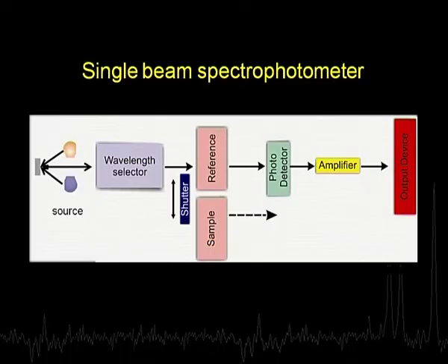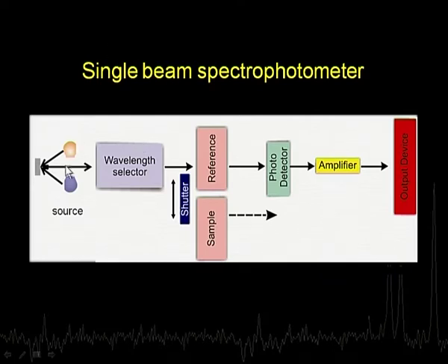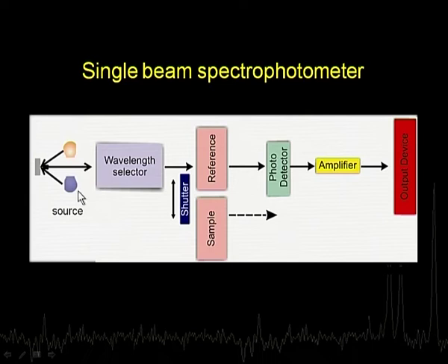The first is the single beam spectrophotometer. You have a source - since we are talking about a UV visible spectrophotometer we need two sources, because a single source cannot give radiation right from 200 to 800 nanometers. So we use a deuterium lamp which gives radiation from 200 to 400 nanometers, and a tungsten lamp which gives radiation from 400 to 800 nanometers. Depending on which region we want to use, we select the appropriate source, and there is provision for switching between the two sources.